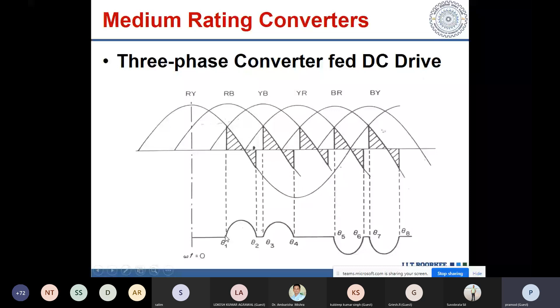If you see the rippled current, it has pulses like this, rather than a quasi-square. The harmonic spectrum of this will be different from the harmonic spectrum of the quasi-square. In the literature, methods are there to find the harmonic spectrum of such types of current, whether your current is continuous with ripples like this, or constant. If it is constant, yes, the fifth harmonic is 20%, 1/5. The seventh harmonic is 14 point some percent, 1/7. The 11th harmonic is 9 point some percent, 1/11. But if the current has ripples, then in terms of the ripple ratio, the harmonics are like this. You can notice that the fifth harmonic keeps on increasing as the ripple increases. The seventh harmonic also increases, the 13th harmonic also increases. So it is difficult to say what the harmonic spectrum will be if the drive is operating in this mode.